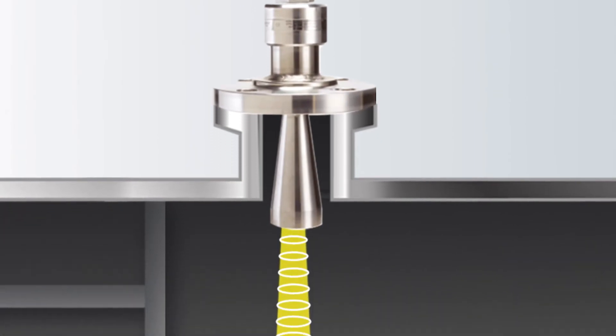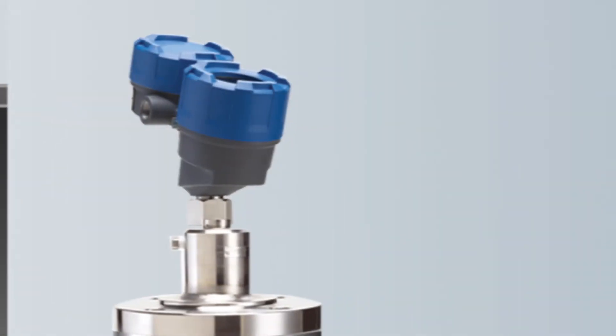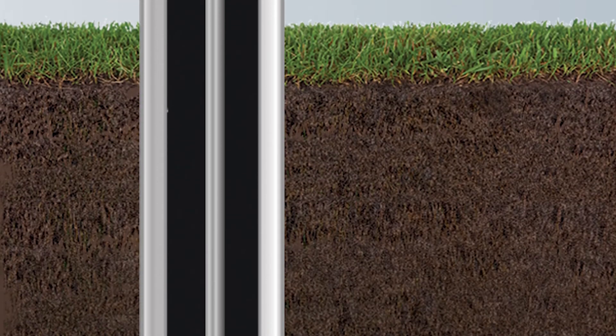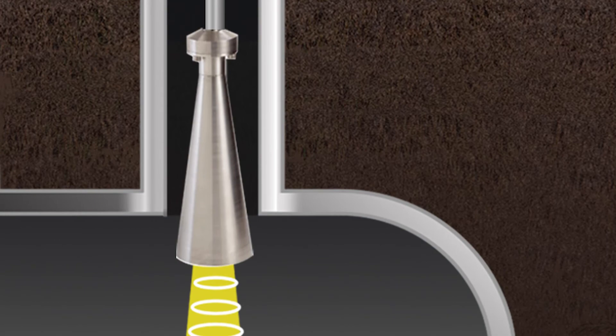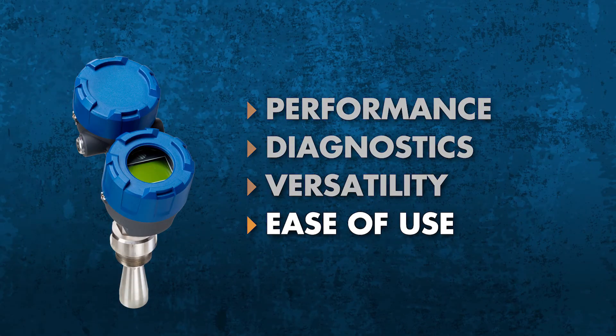Pulsar antennas are up to the task, and the smaller antennas can be installed into process connections as small as one and a half inches. In addition, there are nozzle extensions from four inches to 72 inches, so underground vessel standpipes are never a problem.